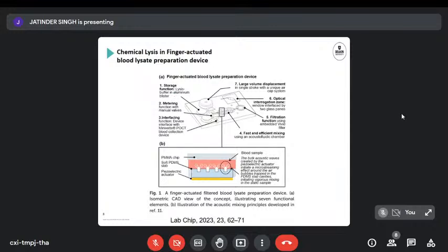Metering is to make sure all the volumes are there. This is a fairly advanced device. So we already have compartments in there with blisters that contain the reagents. And in this instance, it's a commercially sourced lysis buffer.